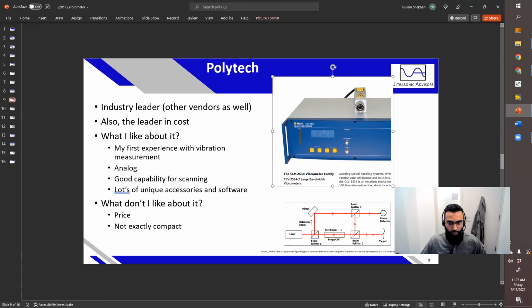So I don't like the price. The price is $20K or $30K plus, and usually even for the basic module for scanning, it can get into the $300,000 range. So it's definitely for research institutions almost always, although there are production environments—I've personally witnessed this from previous industry positions—that use scanning vibrometers on every transducer shipped, to ensure there are no spurious modes. That's simply because of the high power used for those transducers; there's no room for known defects to be present. So the higher power your transducer is, the more characterization you'll need to ensure everything is working smoothly and correctly.